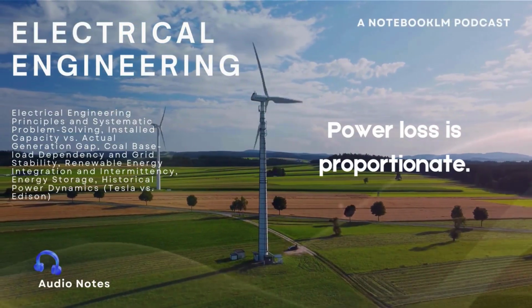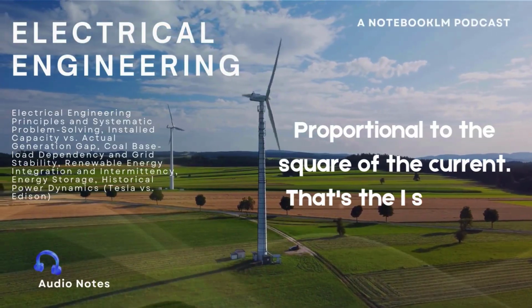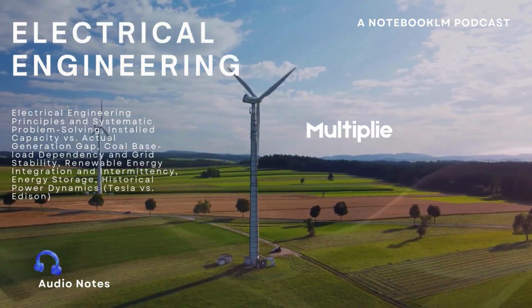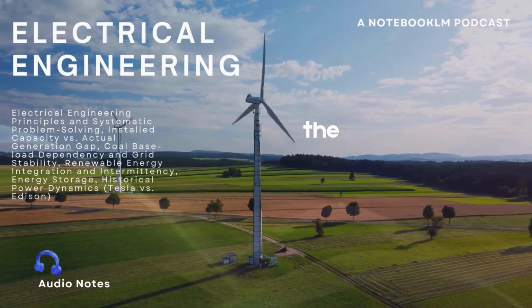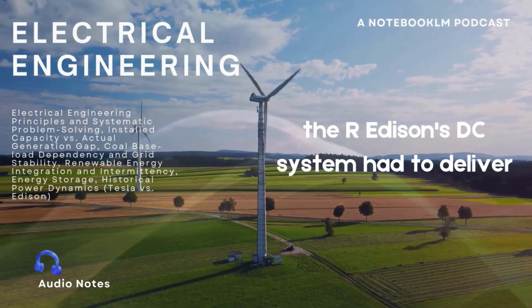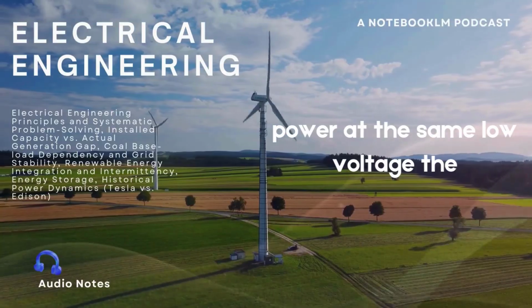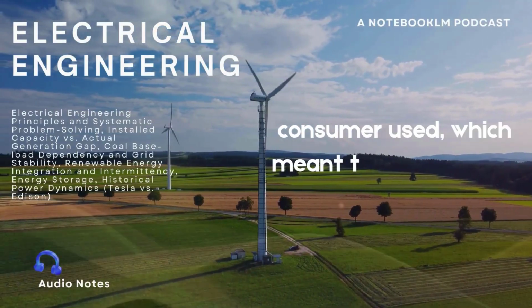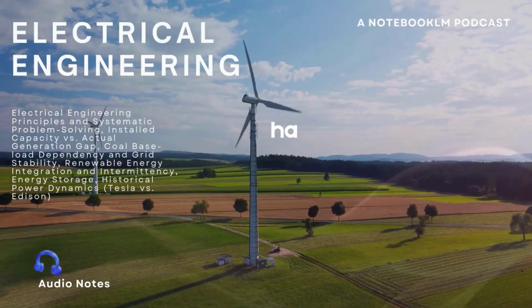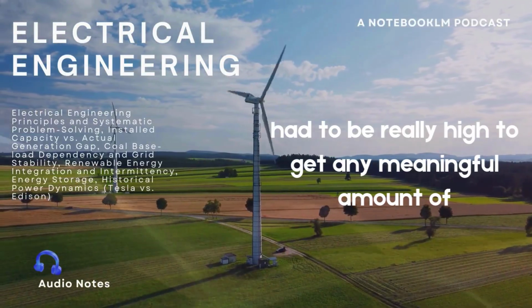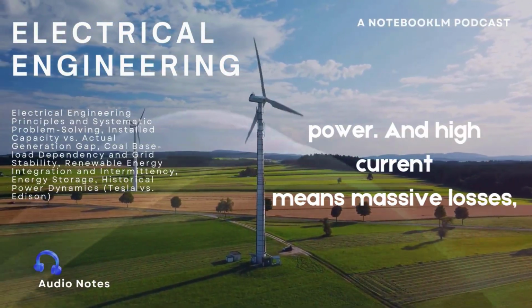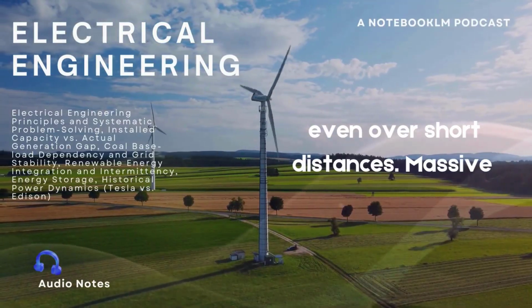Exactly. Power loss is proportional to the square of the current. That's the I², multiplied by the resistance of the wire, the R. Edison's DC system had to deliver power at the same low voltage the consumer used, which meant the current, the I, had to be really high to get any meaningful amount of power. And high current means massive losses, even over short distances.